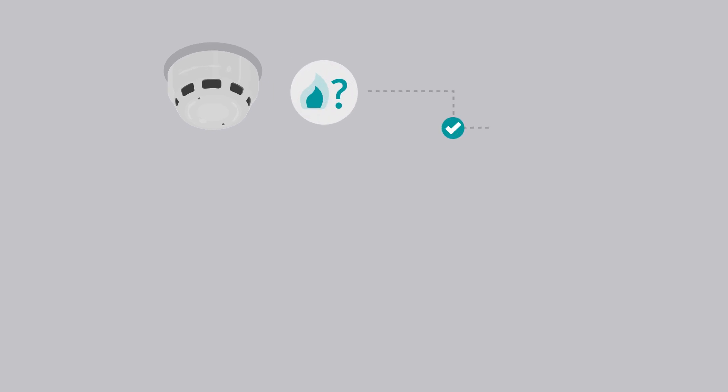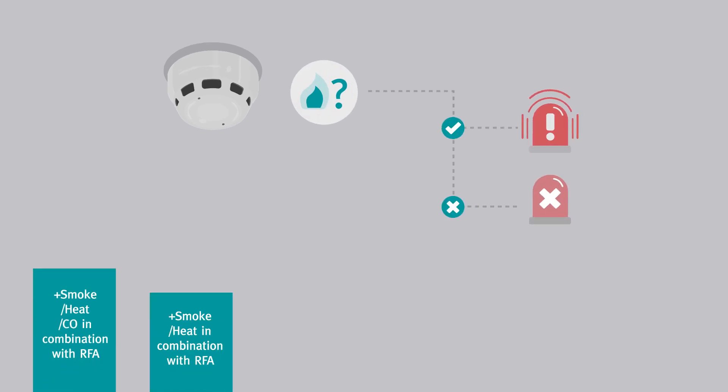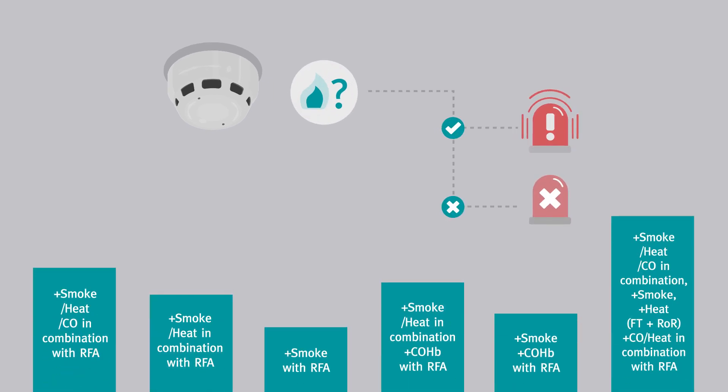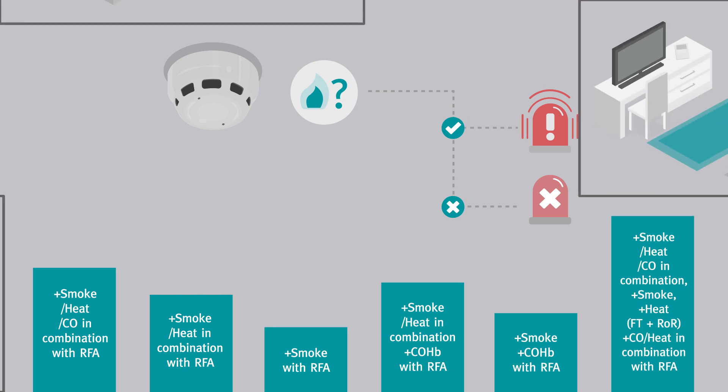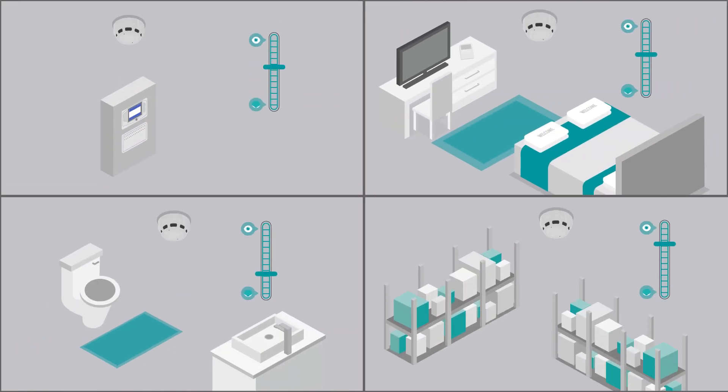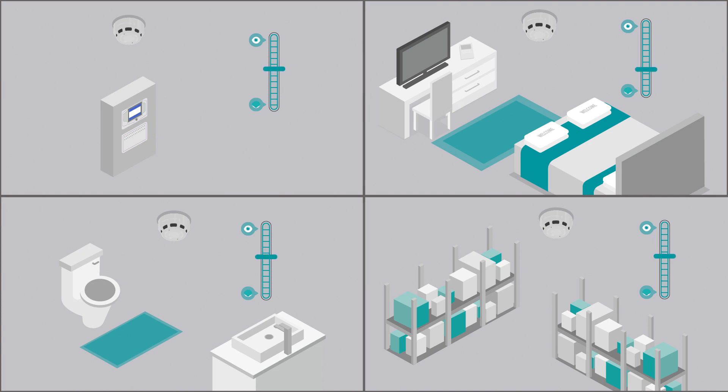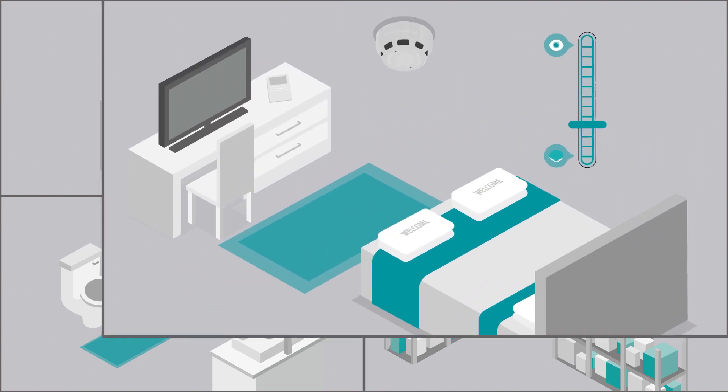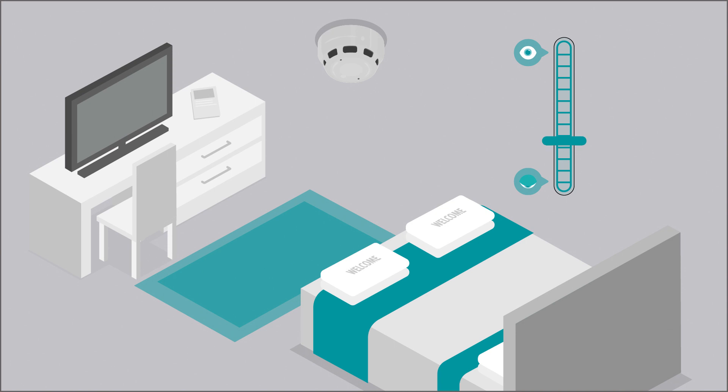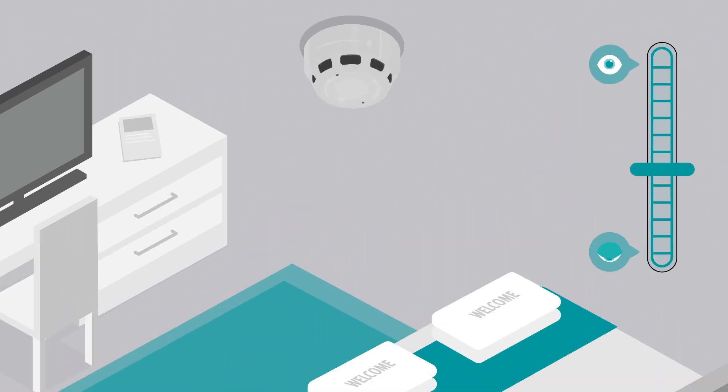The ACD is also enhanced for false alarm reduction. In the modes featuring the reduced false alarm function (RFA), the sensor will automatically adjust the sensitivity of the optical sensing element over time, learning from its surrounding environment from the moment of installation.